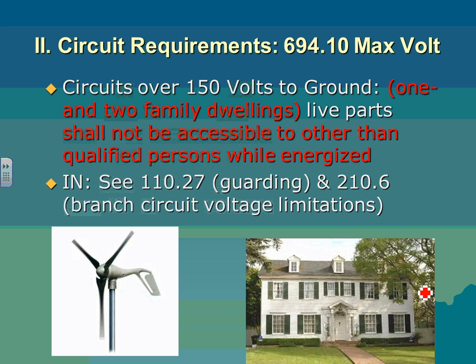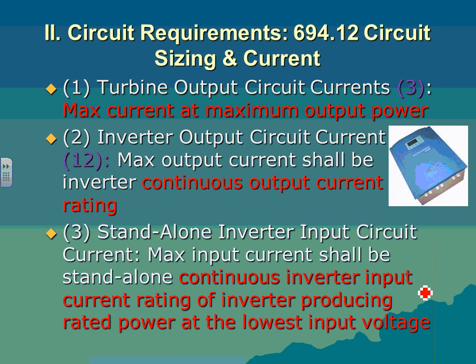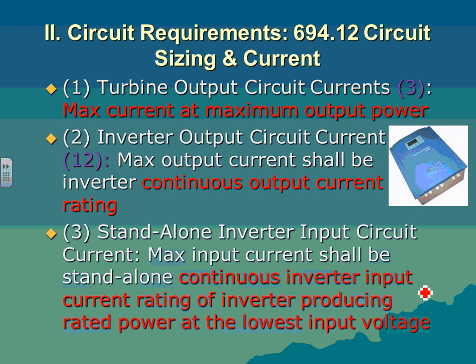You do commercial, industrial, the limit is the sky for that one. And then this is talk about the sizing, guys. I walked you through a lot of these, the sizing. Turbine output circuit, if you don't believe what I wrote on that first slide, I refer you to number 3. If you remember, number 3 says the maximum current at maximum power output, which is 25 miles per hour, I believe. So that's how they define the turbine output circuit.